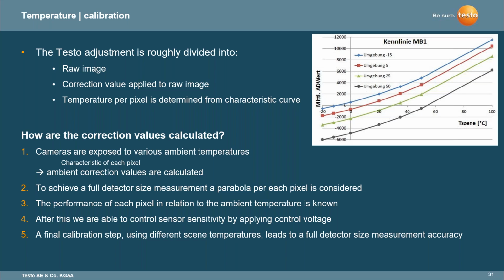To achieve a full detector size measurement, a parabola per each pixel is considered, as you can see in the right-hand graph. The performance of each pixel in relation to ambient temperature is known. After this, we control sensor sensitivity by applying a control voltage to that board, making sure we get that accurate image and the accurate readings we need.